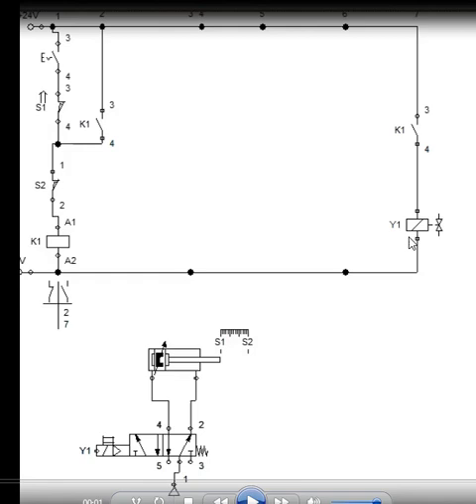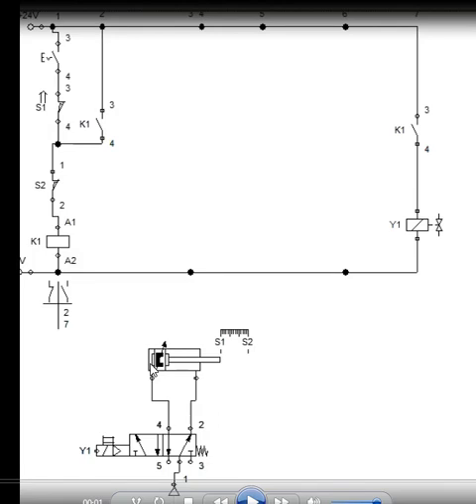As soon as the Y1 gets current, this Y1 solenoid which is getting the current will take this position and as soon as it takes this position, the air will be supplied on this side of the piston, that is the head of the piston, and the piston will move towards the right. It will move from S1 to S2.